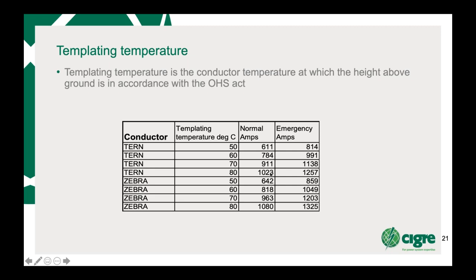And the reason for that is that it just takes a higher temperature to get to the particular object height above ground clearance. So all the templating temperature does is that it lifts the conductor higher above the ground, and it then allows you more current to flow down before the templating temperature is reached. And in South Africa, we don't go above 80 degrees C, really due to the uncertainty in variation in the ambient conditions, which may cause a conductor to go above 80 degrees C, up to 120 or 100 degrees C, for a short period of time. That might cause annealing. So unless you have real-time monitoring on the system to limit it above that, it's not recommended to actually go above 80 degrees C templating.